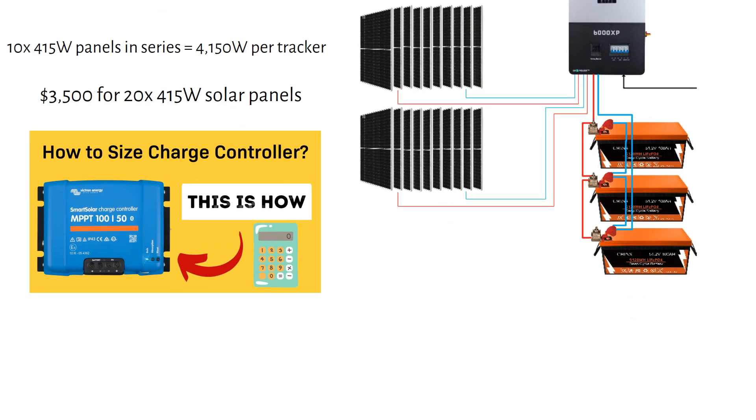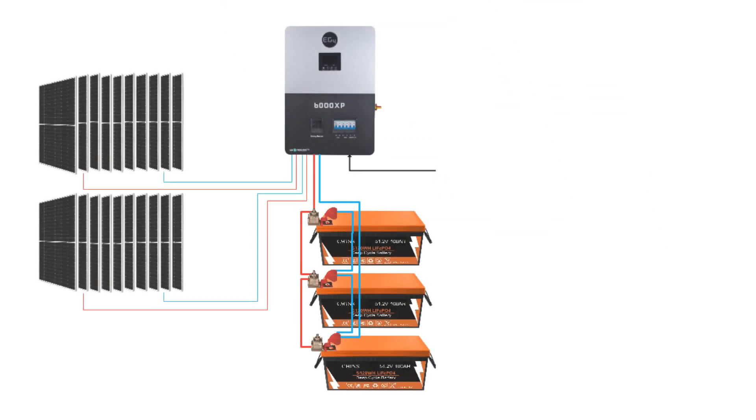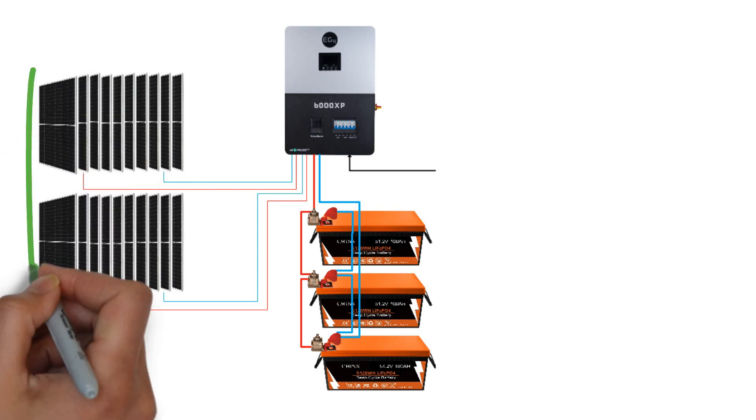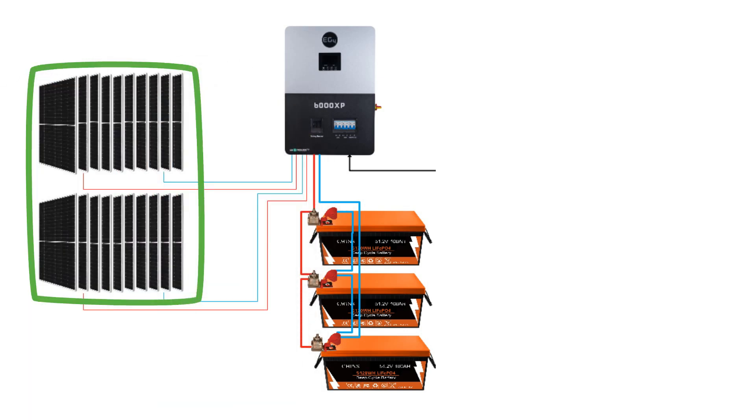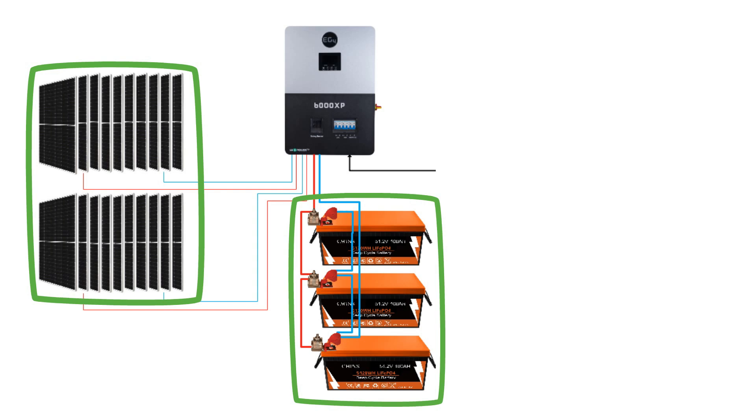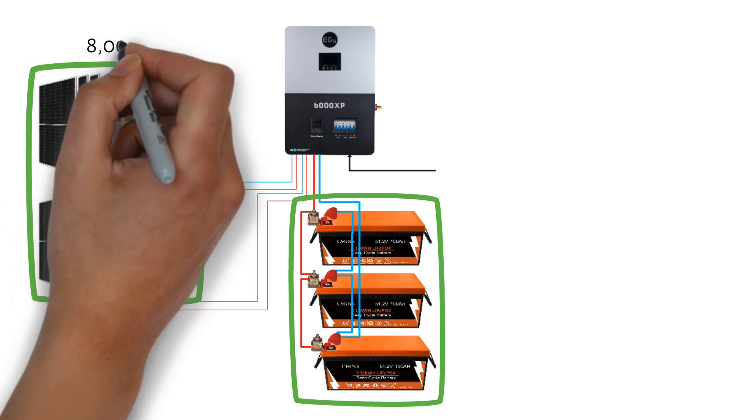Let's calculate the wire and fuse sizes. We have to figure out where the most power comes from. From the solar panels into the batteries or from the batteries to the inverter.